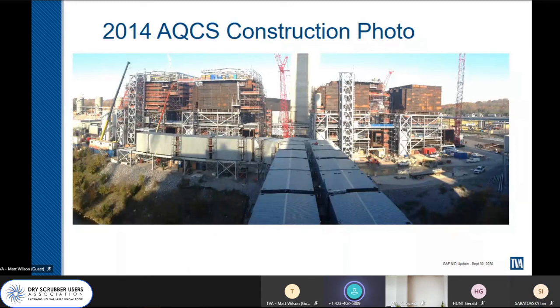All right. As far as insulation, and I point this out because it's interesting and deals with corrosion. So our specification called for 4 inches of insulation. Alstom did comply with that, of course. The ductwork that you see in the foreground here has 4 inches of insulation. Anything hot had 4 inches of insulation, but then Alstom doubled the insulation on all the cold surfaces, so basically downstream of the scrubber. Why was that? Because they wanted to ensure that that metal stayed warm enough that it would not lead to acid gas corrosion attack during the operation of this unit. So we've got 8 inches of mineral wool insulation on all the cool surfaces, and that's an Alstom specification.